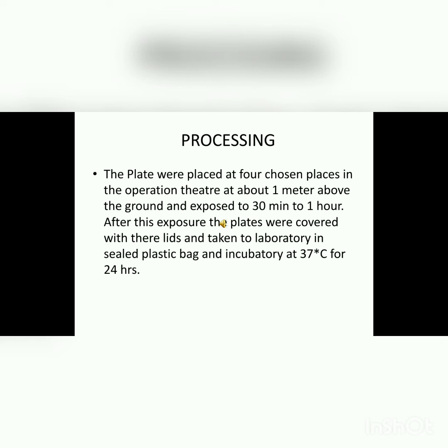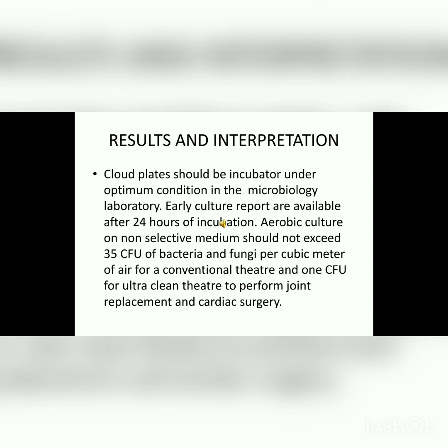Then the processing of the first one, the sedimentation method. The plates were placed at four chosen places in the operation theater at about 1 meter above the ground and exposed for 30 minutes to 1 hour. After exposure, the plates were covered with lids and taken to the laboratory in a sealed plastic bag and incubated at 37 degrees Celsius for 24 hours.